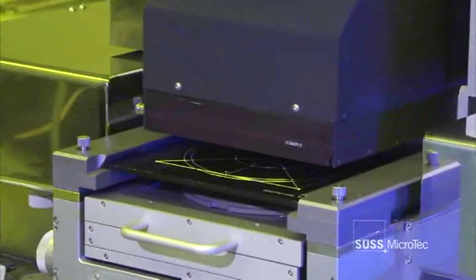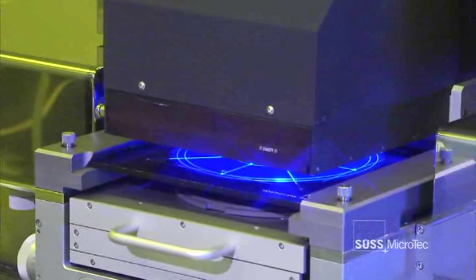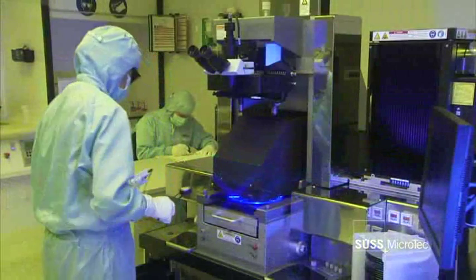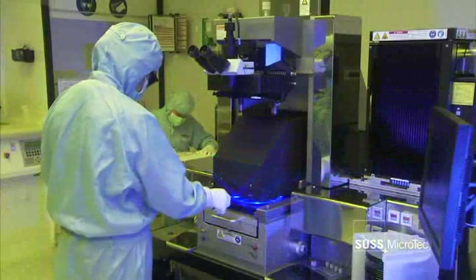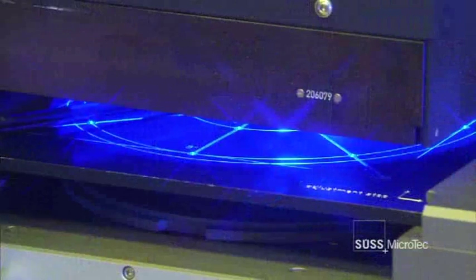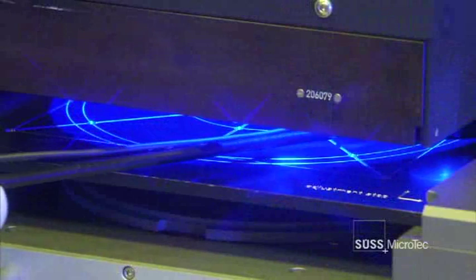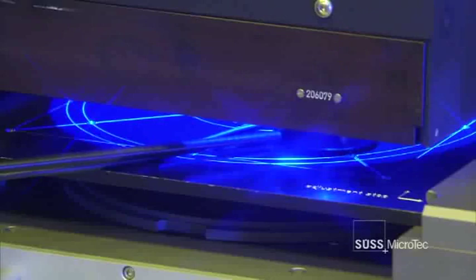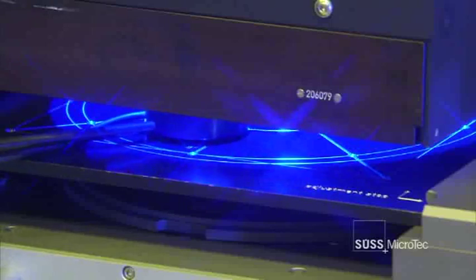An important improvement with the new lab aligner platform is the SUSS constant dose exposure mode. It accurately controls the exposure dose by adjusting the required exposure time. Advanced exposure dose control coupled with improved light uniformity across the whole wafer lead to a process control that has never been reached with a full-field aligner before.